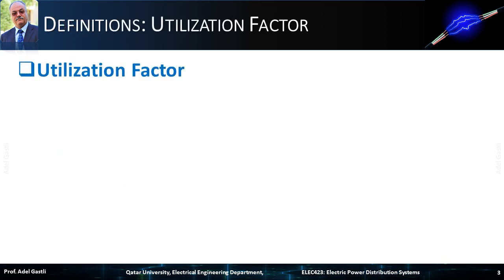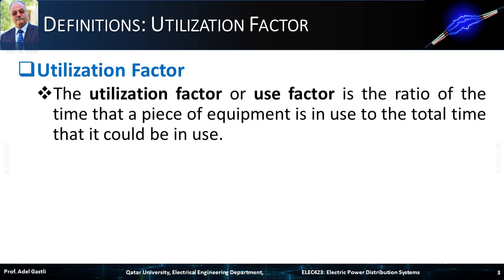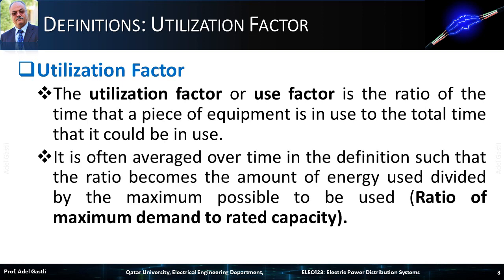Let's start by defining the utilization factor, or use factor. It is the ratio of the time that a piece of equipment is in use to the total time that it could be in use, called base time. It is often averaged over time such that the ratio becomes the amount of energy used divided by the maximum possible to be used — that is the ratio of maximum demand to rated capacity.